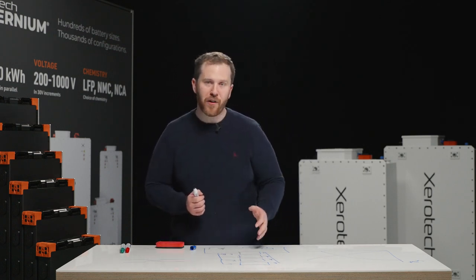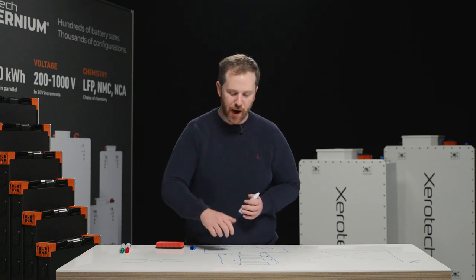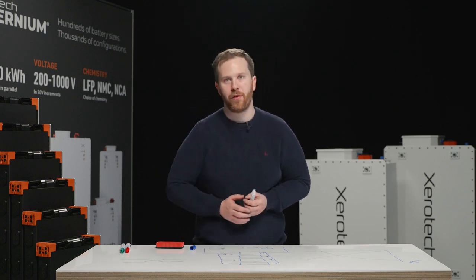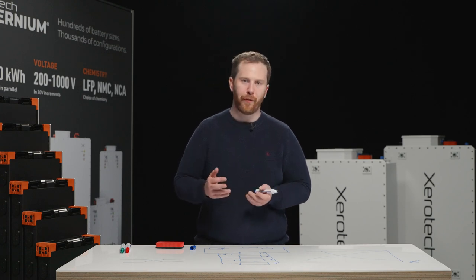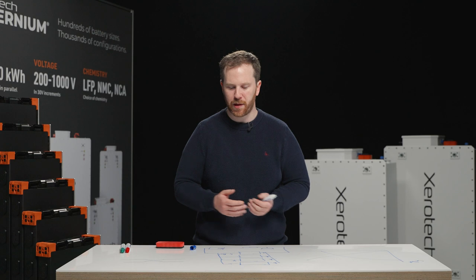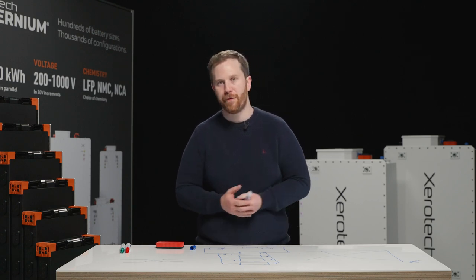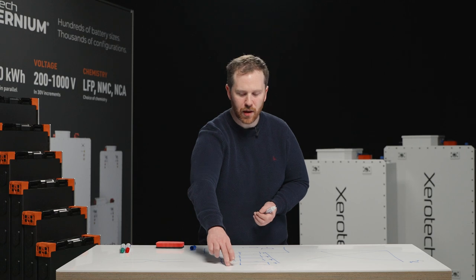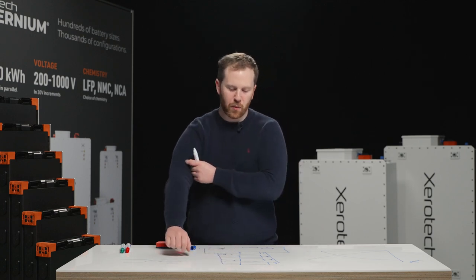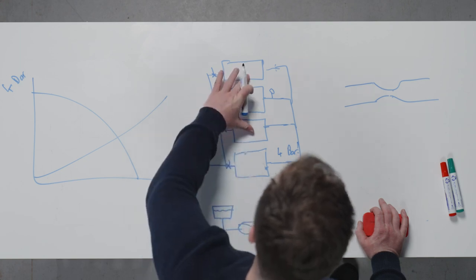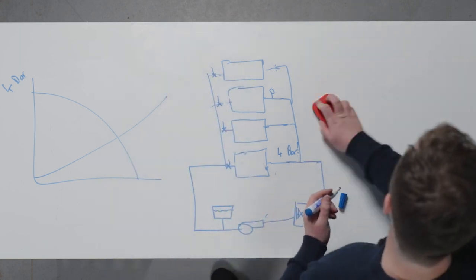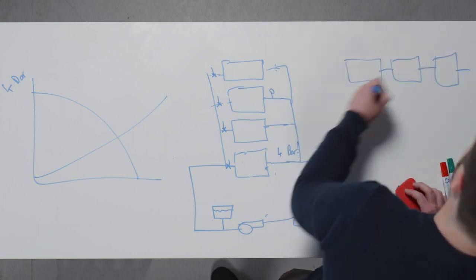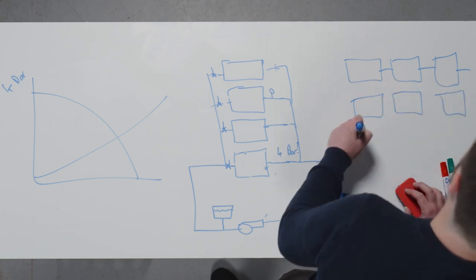We'd also add that for very large scale systems, it may not be practical to put all the packs directly in fluid parallel. So for example, for very large energy storage systems, rail applications that might have 20, 30, 40 packs, it could be quite challenging to have so many parallel paths, because what will happen here is that pressure drop will be so low, it'll be very hard to develop the required flow rates through them. So sometimes you can have a parallel series arrangement that looks something like you've got maybe 3 packs in series and then many more packs in parallel.